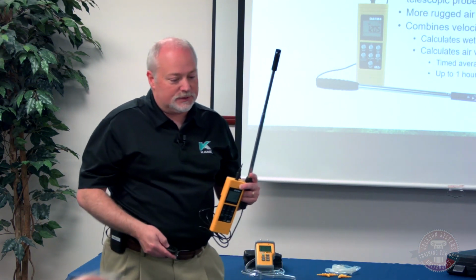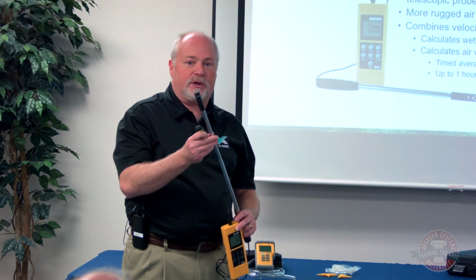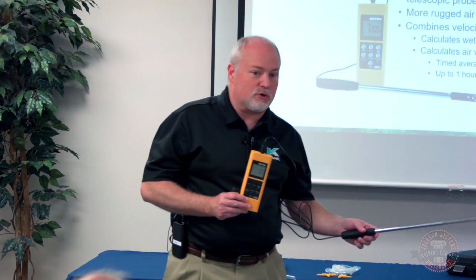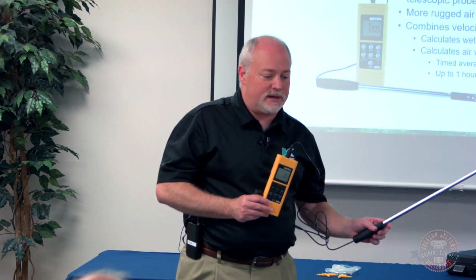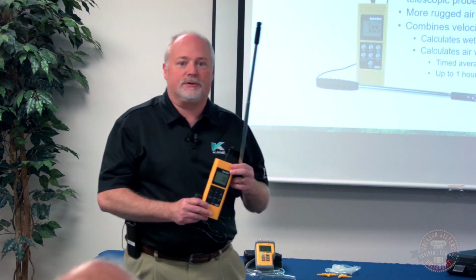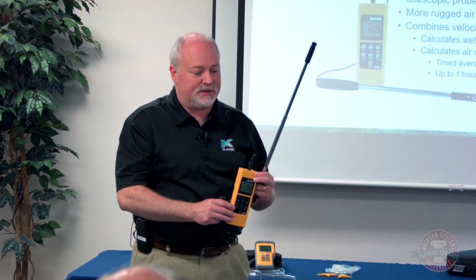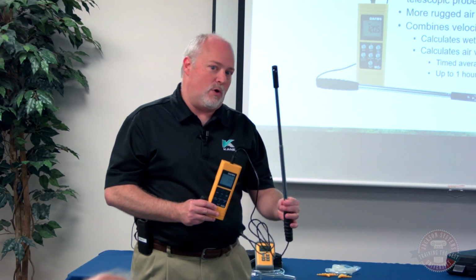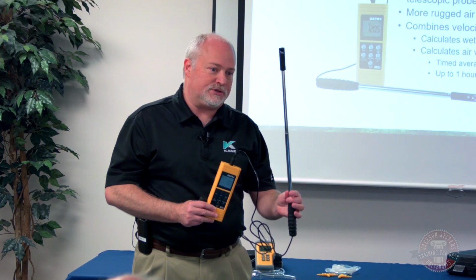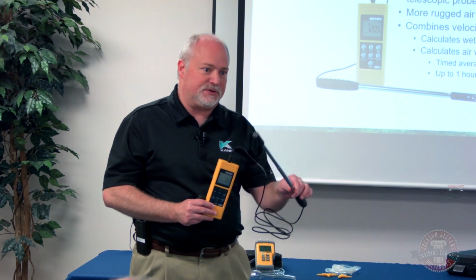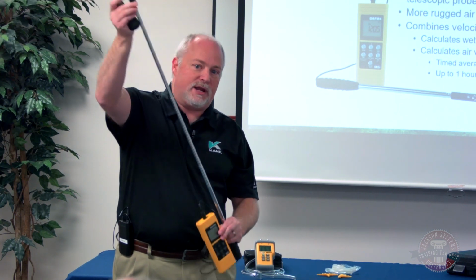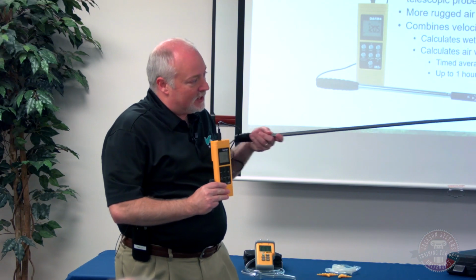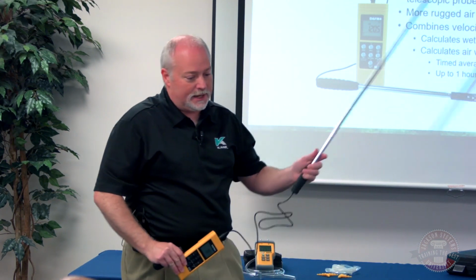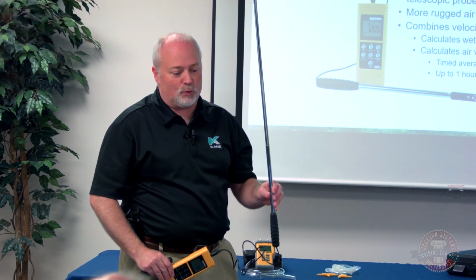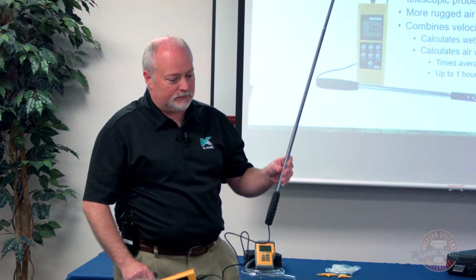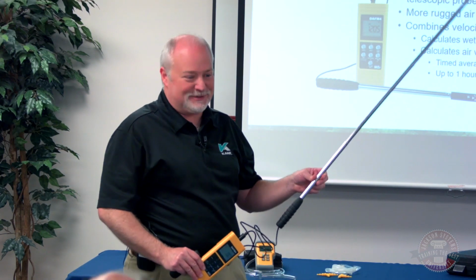Some of the uses there are surface or in-duct measurements. We can go over to a supply air or a return air grill and read what's coming out of the surface, or, and we'll walk through this later on, we can do an in-duct measurement by drilling some access holes in there. The nice thing is, as you can see, this is a pretty small head on this anemometer, so you only need a 3/4 inch opening in that duct to insert it. It extends out up to 39 inches in length, so we can get across a pretty good sized duct to take that reading to get our good average. The advantage of the vane style is they are more rugged than the hot wire instrument. Being rugged is a good thing in the back of a service truck with your tools.